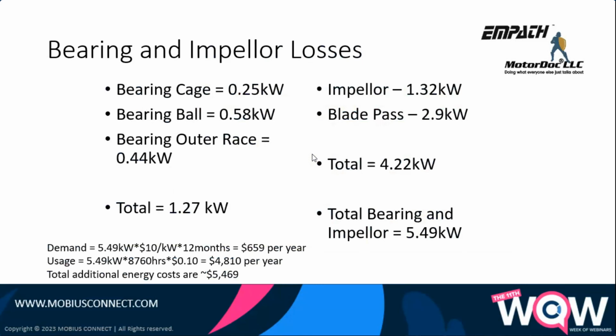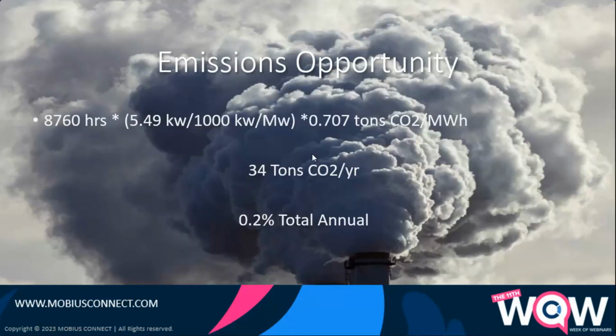So the total losses in the impeller and blade pass were 4.22 kilowatts, or 4.25 kilowatts on that machine, because of a ding on the blade. That was it. Maybe some other stuff, but primarily it was the ding on the blade. And then the bearings, which were failing because they weren't lubricated properly, was 1.27. That came out to $5,500 per year for that little ding. Instead of correcting it, they left it. And 34 tons of CO2 per year.